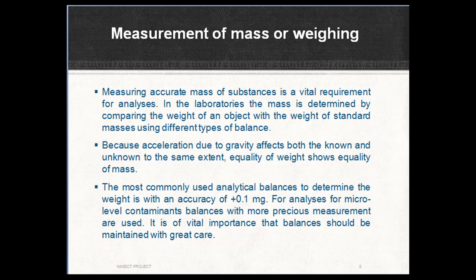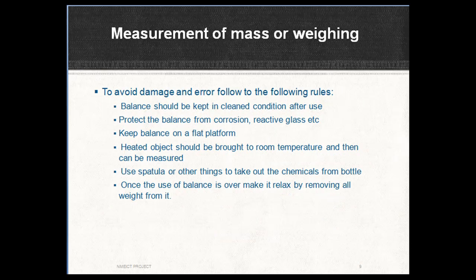It is of vital importance that the balance should be maintained with great care. To avoid damage and error, follow these rules: the balance should be kept in a clean condition after use; protect the balance from corrosion; keep the balance on a flat platform; heated objects should be brought to room temperature before being measured; use a spatula or other implement to take out chemicals. Once use of the balance is over, relax it by removing all weight from it.